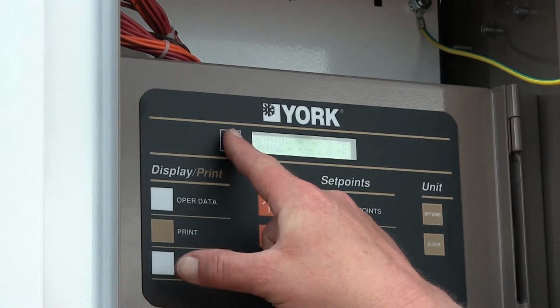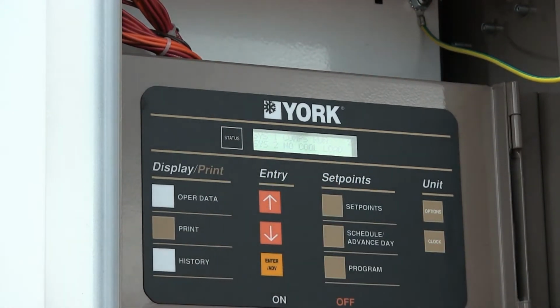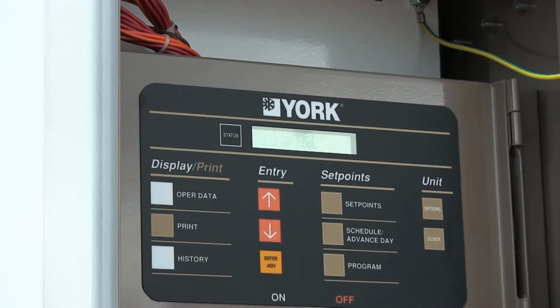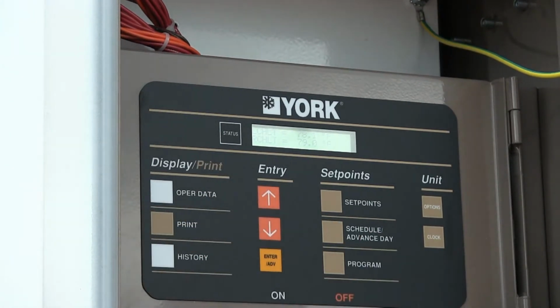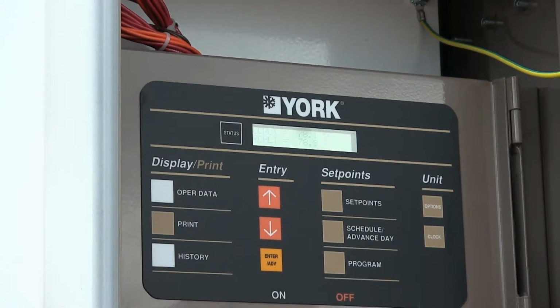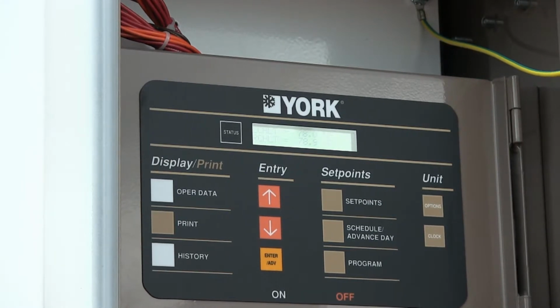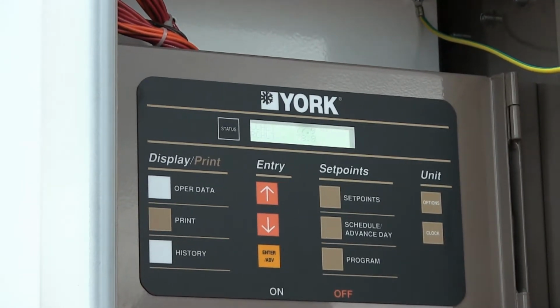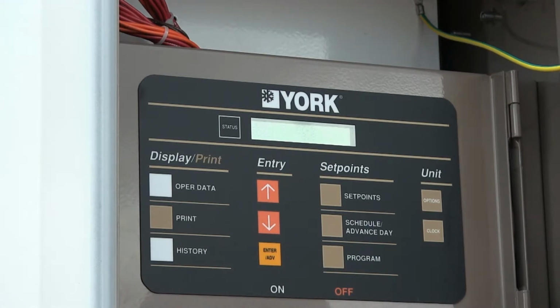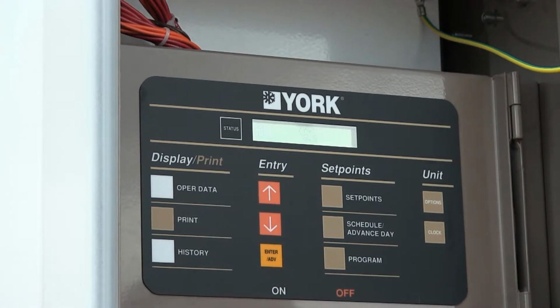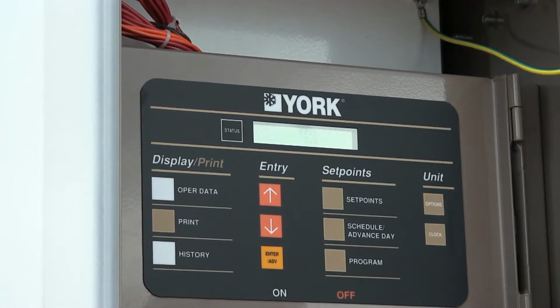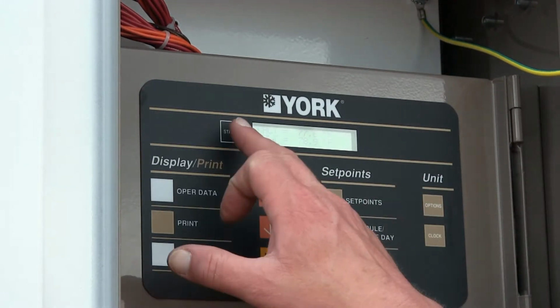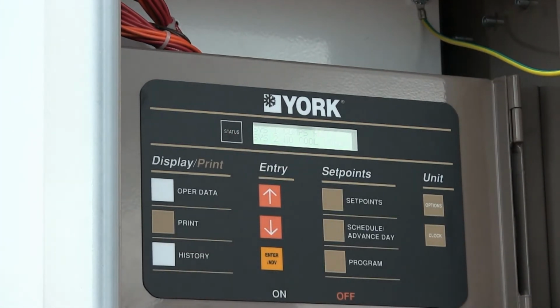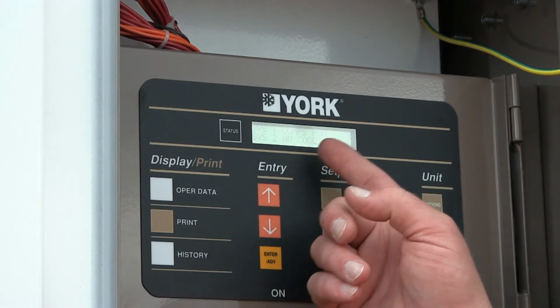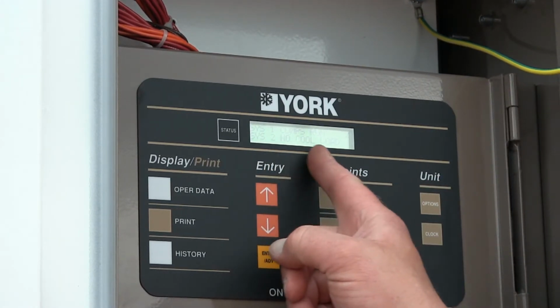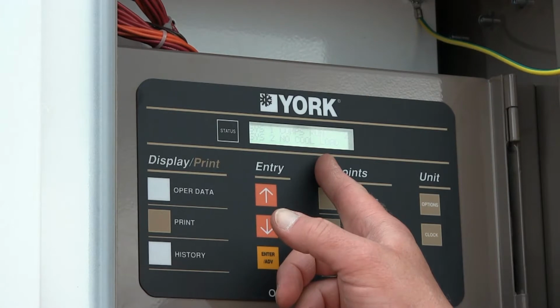So we started up the compressors. Now we have 2 compressors running on circuit 1, and you'll continue to watch the liquid temperature drop. We're already down to 78 degrees. It'll take about a couple of minutes for it to continue to load compressors, but as they continue to load, the temperature will drop lower and lower. So to kind of recap, if you get lost in here, just go back to your status screen. It'll tell you what it's doing. System 1's got 2 compressors. It's waiting on system 2, even though it has a full load on it.